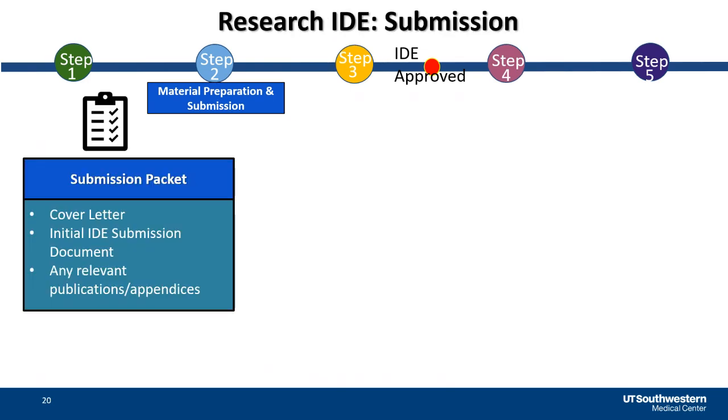Okay, so now we can put together our submission packet. We have our cover letter, our initial IDE submission document, the big document with all the different sections, and then any relevant publications, appendices, letters, anything else that you need to pop in.